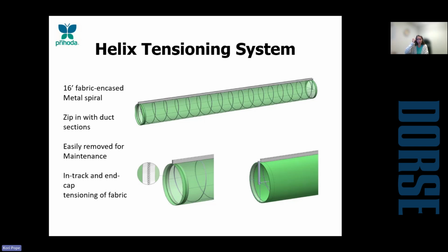However, if you are in an application where you need the duct to be held fully open regardless of that unit being on or off, we do have our Helix tensioning system. So this is a 16-foot fabric spiral that is located internal of the duct. Our Helix tensioning system is our top of the line tensioning system that we offer, and it is going to hold the duct open no matter if that unit is on or off. The way that this works is it has that same in-track tensioning system as well as an end-cap tensioner right here at the end. So it's actually pulled completely taut.